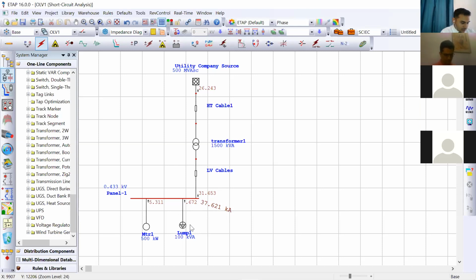When a short circuit is happening on the bus bar, there is a common theory that all motors will feed to the short circuit location. Here the short circuit location is bus bar. So this lump load percentage motorized load will feed to this point. Similarly, this 500 kilowatt motor will also feed to this. Of course, their feeding has got a limit based on their own percentage impedance. This is calculated by ETAP, and the total short circuit current this bus bar is facing right now is 37.621 kiloampere. This is the summation of 31.653 plus 0.672 plus 5.311.